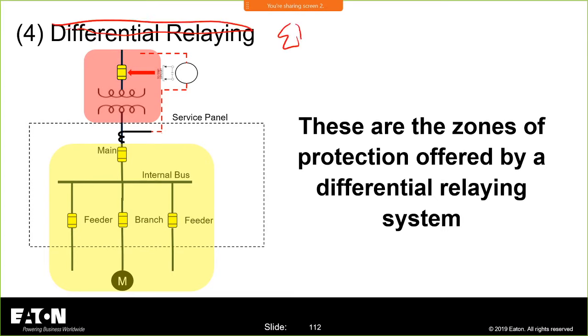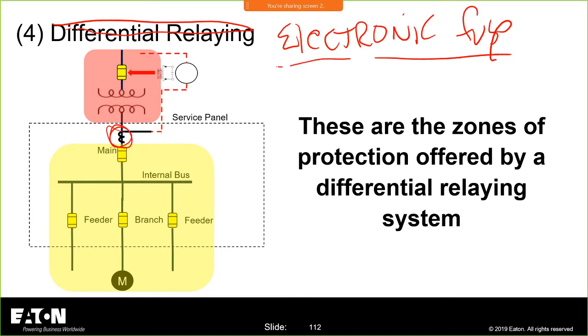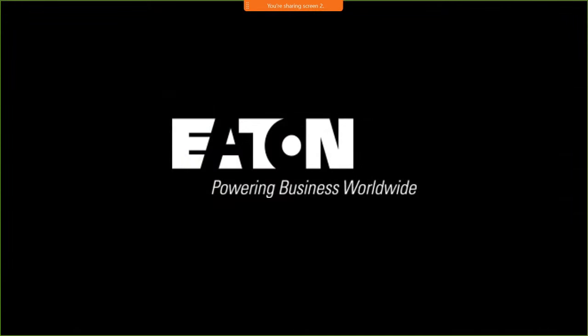This is the electronically actuated fuse. Electronic fuse. What happens here is you have the sensor on the secondary, and right now the only place this exists is as a medium voltage fuse. You have a CT here. You have a brain here, the relay. When it determines that your current value goes greater than a certain number, it will tell that fuse to open using pyrotechnic, right? It's not a Star Wars thing. It's a charge inside that fuse, and it tells it when to open.